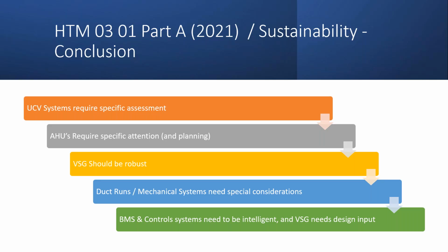So HTM 03-01 Part A, 2021, sustainability conclusion: we need to look at UCV systems and the specific assessment. Remember ductwork and where it sits. AHUs require specific attention and planning if going outside, heat tracing, etc. The ventilation safety group has to be multidisciplinary, not just one authorising engineer running the show, it's got to be multiple people. Duct runs and mechanical systems need special consideration. BMS and control systems need to be intelligent, and the VSG needs design input, but it can't just be left to the designer, it's a full group effort to get these things to work correctly.